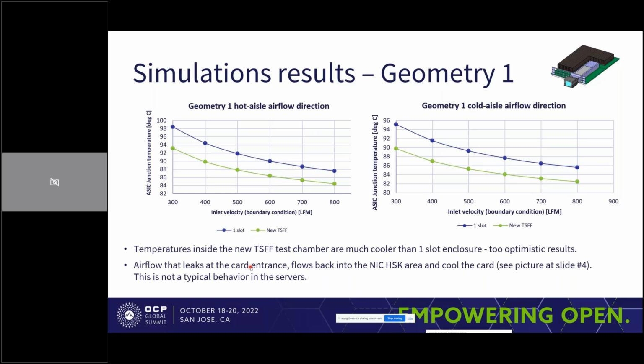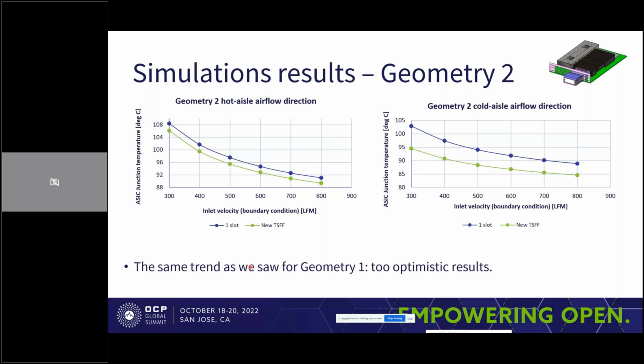And for geometry 2, we see a similar trend. Although here for hot aisle airflow direction, these two curves are much closer to one another, but for cold aisle we see a bigger difference, almost 10 degrees Celsius, 8 or 9 here for 300 LFM, for example.